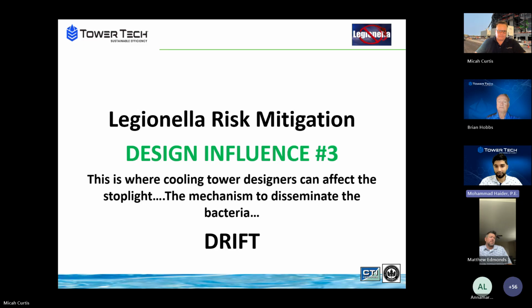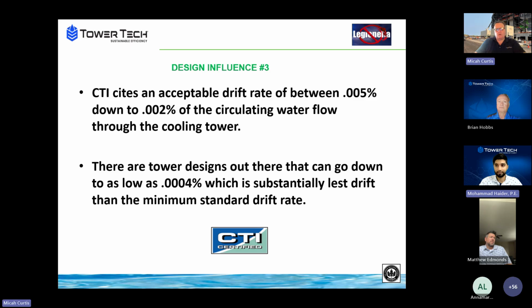And I believe we're going to get on to the actual rates here. So, Mohammed, what's an acceptable drift rate per Cooling Tower Institute? Yeah, so CTI, which is the Cooling Tower Institute, the typical acceptable rate for drift is 0.005, and some towers get down to 0.002. Now, there are tower designs that can go much lower than that, at 0.0004, which is a substantially lower amount of drift.